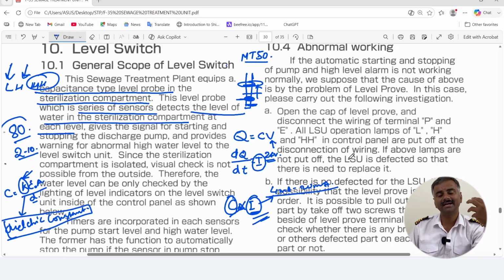If you correlate it with the water transducer in the purifier, it will be more clear. Say if water is not coming and only pure oil is going, it has a different dielectric. When water comes along with oil, the dielectric changes, the current changes, and the capacitance changes. As the capacitance changes, your value changes, and it gives an alarm. The water transducer gives an alarm.